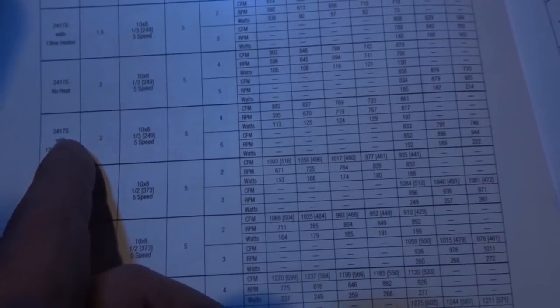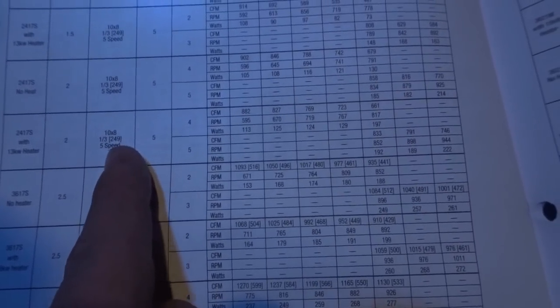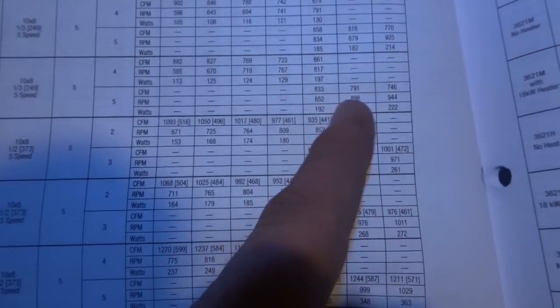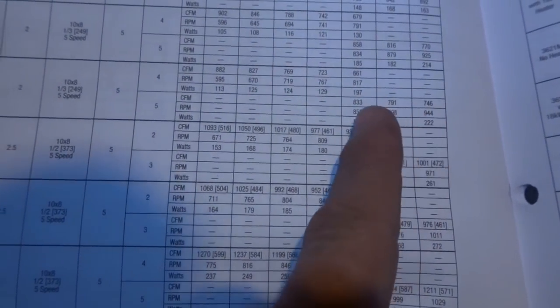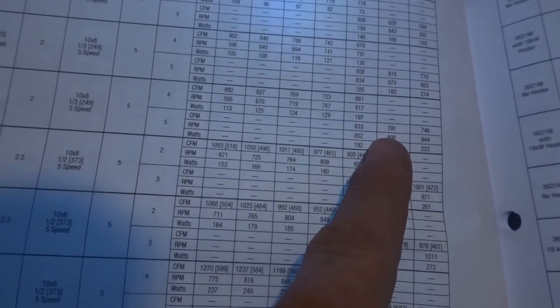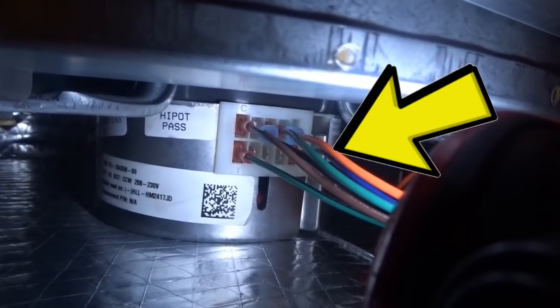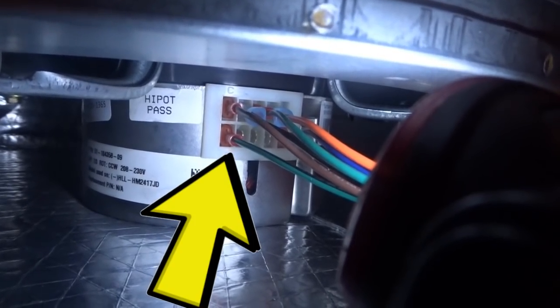We're looking at the blower speed charts here. I'm looking at the 2417S with 13kW heat strips, 2 tons, 10x8, 1/3 horse, 5-speed. At 0.5 to 0.6 static, that's probably where we're going to end up — so between 0.5 and 0.7 is our sweet spot on high speed, which is speed 5. We'll turn it on to 5 and make sure we're getting right around 800 CFM for our two-ton unit. Our blue wires are already set on speed 5, and the green wire is our fan-only speed.